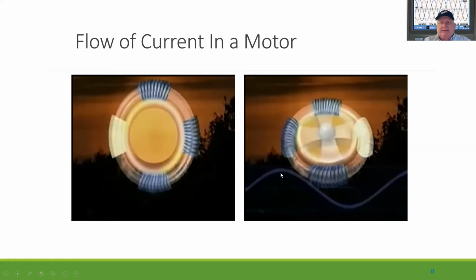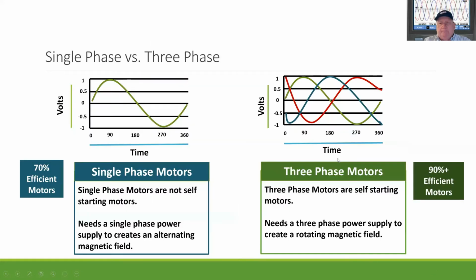And what ends up happening is the motor coils are actually changing from north to south, and they continue to rotate and make the motor turn. So we have single phase power, which drives single phase motors, with one sine wave, which is basically two legs of the three phase power, and it only requires two power lines. The issue is single phase motors on average are 70% or less efficient. So that's why they've gone to three phase as much as possible, but it is more costly to bring your lines out to the customer, and that ends up being about a 90% efficient device. So that's why a lot of people want to use three-phase motors, especially in larger horsepower, because there can be as much as 20% difference just in the efficiency.